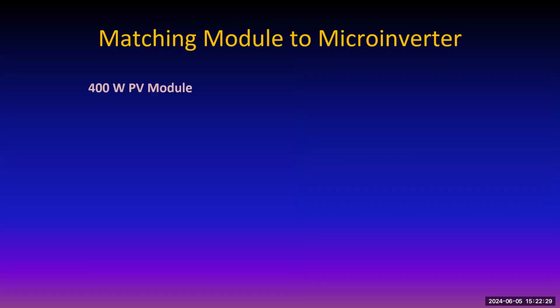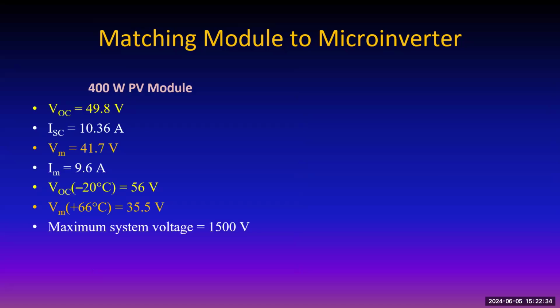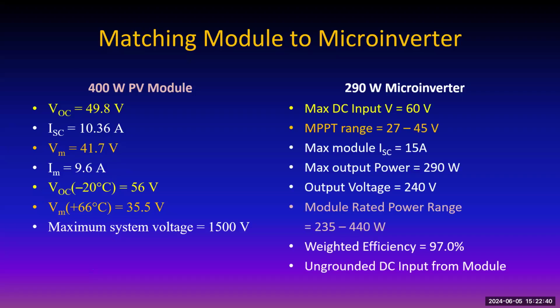Okay, but now we're going to apply these design rules. We're going to take a 400-watt module that's characterized with the following properties. We're going to take the 290-watt microinverter and see if it'll work. So look at the yellow. Open circuit voltage on the module is 49.8, maximum DC input 60.